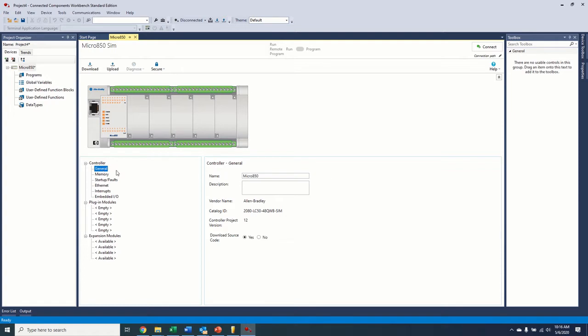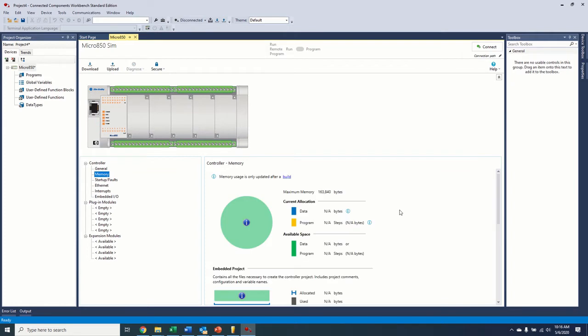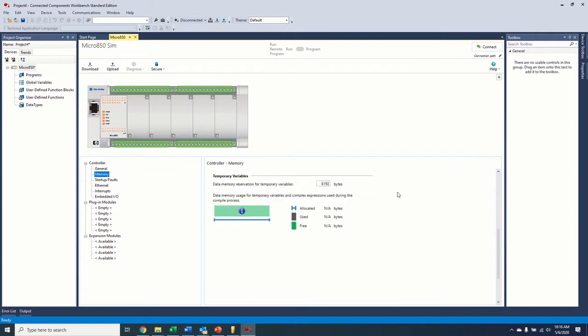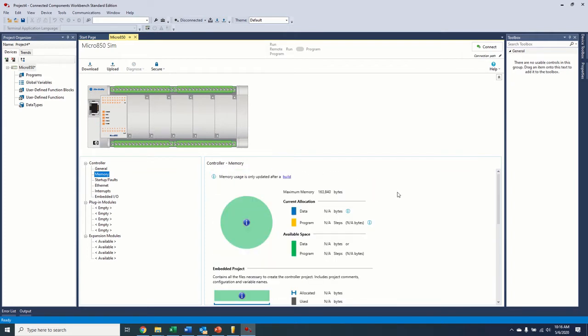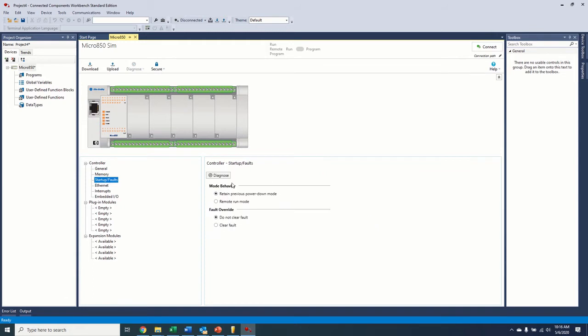So in general, that's where you can rename your controller, whatever you'd like to. Memory, pretty self-explanatory. This is how much you've used, how much is left. Startup and fault. So the mode behavior is what you want it to do on startup. Do you want it to just go right to run mode, or do you want it to assume the same mode it was in when it lost power? And then this fault override, do you want it to try to clear the fault on its own and keep running, or do you want it to wait for operator interaction to clear the fault?